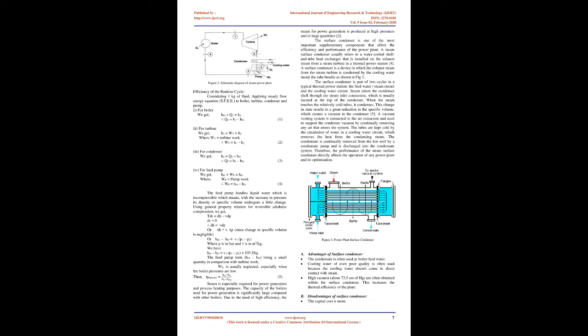5. Steam is especially required for power generation and process heating purposes. The capacity of the boilers used for power generation is significantly large compared with other boilers. Due to the need of high efficiency, the steam for power generation is produced at high pressures and in huge quantities. 3. The surface condenser is one of the most important supplementary components that affect the efficiency and performance of the power plant. A steam surface condenser usually refers to a water-cooled shell and tube heat exchanger that is installed on the exhaust steam from a steam turbine in a thermal power station.